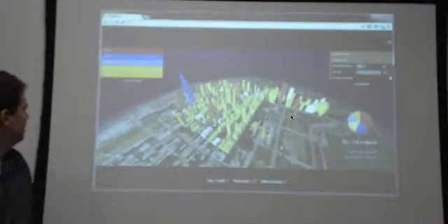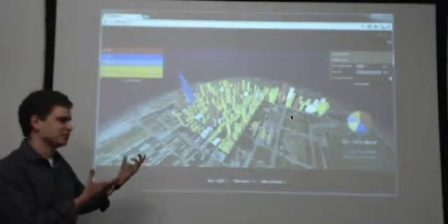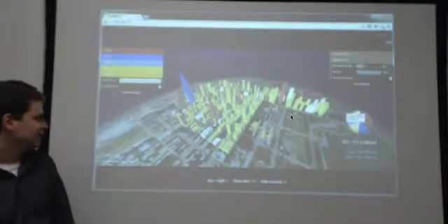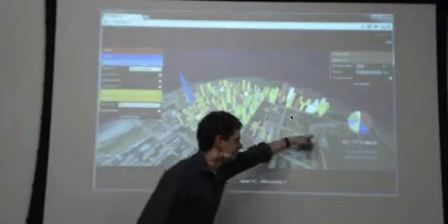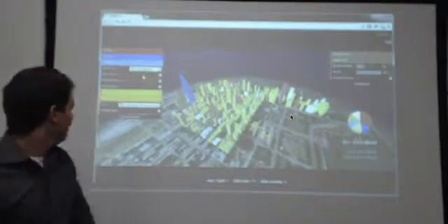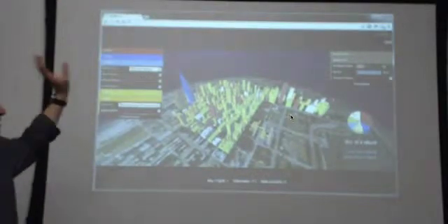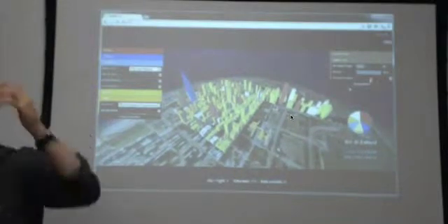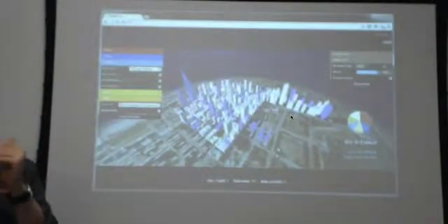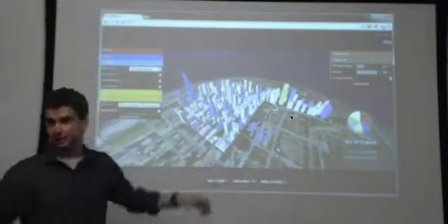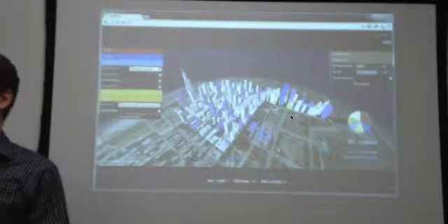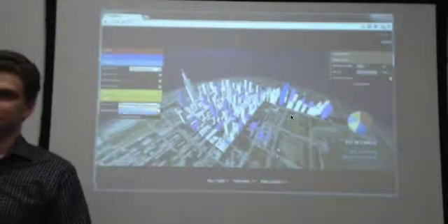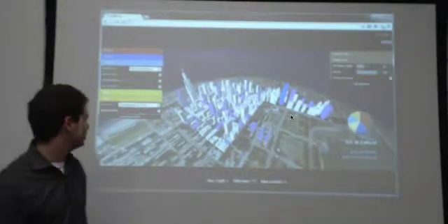and the breakdown. And then I built in a retrofit module that basically allows you to say, okay, if we change the lighting from T12 to LED, it's going to save that white little sliver of energy. And if you add an economizer cycle to that building, it's going to save more energy. There's a collection of 15 different measures in the background, and as I click on a building, I can click those retrofit measures, and it will tell me how much energy savings will be seen in that building. And this happens instantly, because everything's pre-run.